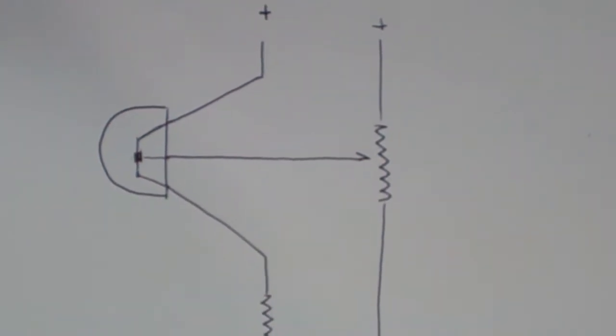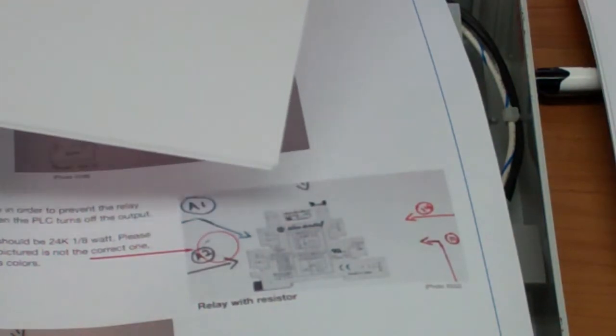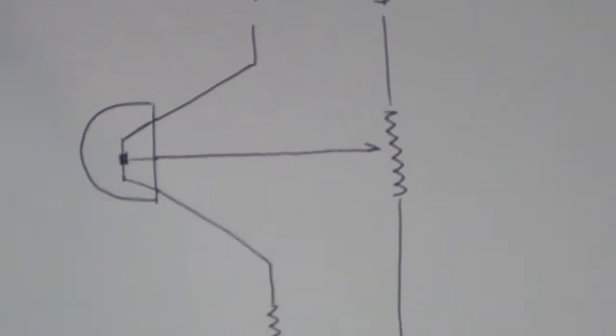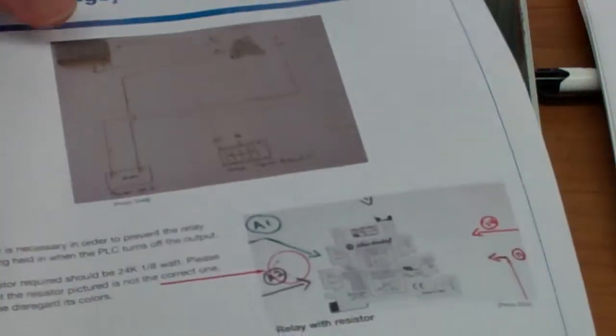Now I know there's a leakage current factor in a transistor, and that can cause issues: you have your inrush current into a relay, your holding current for the relay, and your dropout current for a relay. I asked Allen Bradley up front, I said, guys, I think that if you take this relay...